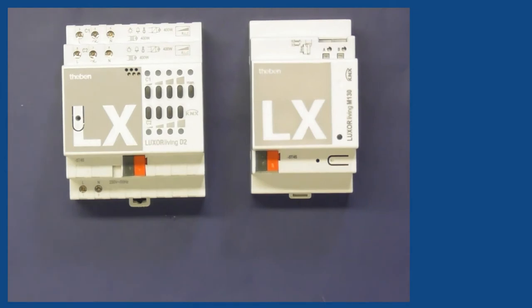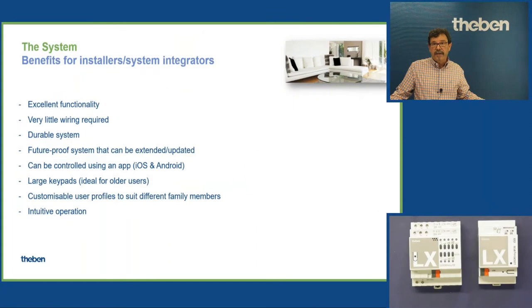On this communication, you get all the data receiving and sending in the entire bus system. What is allowed, what is proven, you are allowed to wire all these in a kind of line cabling in one line. So you loop it just through. You can do the wiring like a tree. You can have some accesses here, left and right side. Everything is fine. But what you have to avoid is the token ring. So you aren't allowed to make a ring or a loop, however you want to describe it. This is a no-go. But line, tree, and all the things around are possible. So it's very little equipment which you need and very little time to do the wiring among these system components in a smart home solution.